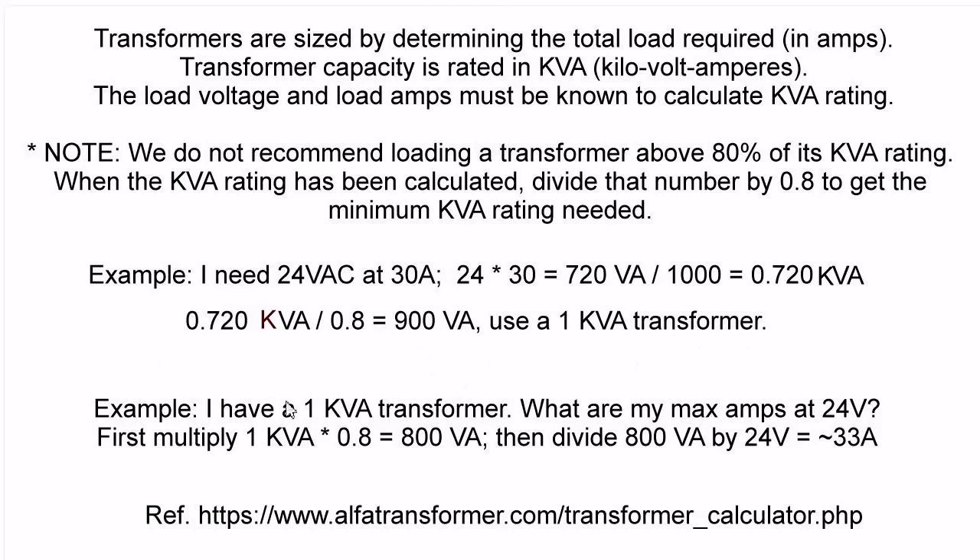Example number two: I have a 1 KVA transformer. What are my max amps at 24 volts? First, multiply KVA by 0.8 and I get 800 volt-amps or 0.8 KVA. Then divide 800 volt-amps by 24 volts and I get approximately 33 amps. That's how it's done. Thanks to Alfa Transformer for the information off their website.